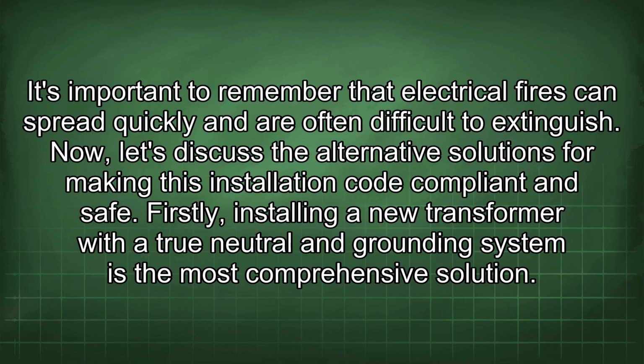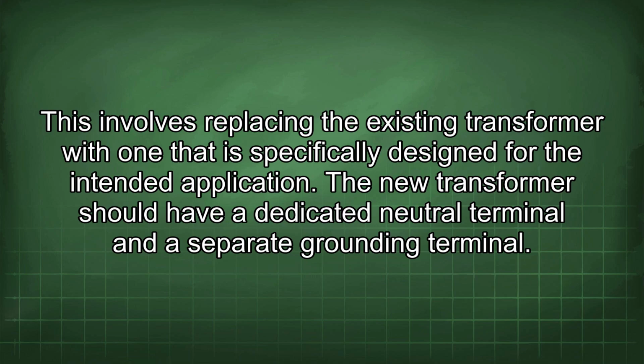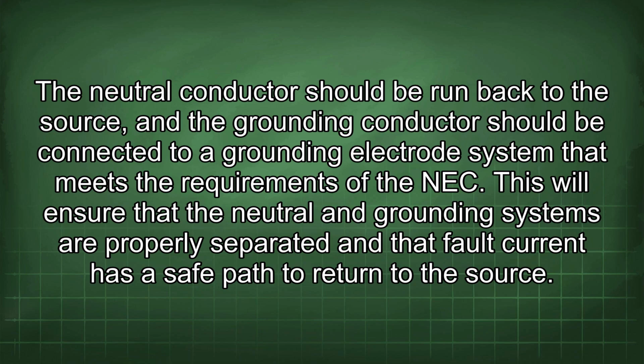Now let's discuss the alternative solutions for making this installation code compliant and safe. Firstly, installing a new transformer with a true neutral and grounding system is the most comprehensive solution. This involves replacing the existing transformer with one that is specifically designed for the intended application. The new transformer should have a dedicated neutral terminal and a separate grounding terminal. The neutral conductor should be run back to the source, and the grounding conductor should be connected to a grounding electrode system that meets the requirements of the NEC. This will ensure that the neutral and grounding systems are properly separated and that fault current has a safe path to return to the source.